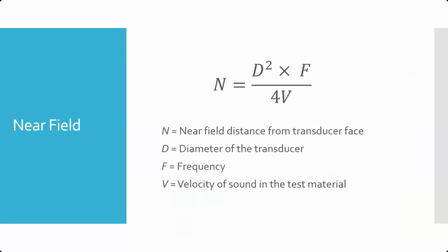So near field, right, the distance of near field, this is the distance from the transducer face. And remember, this is the transducer face, so part of this is going to occur in that wear plate area, right? It's not going to be from the surface of the part, but you have to take into account how thick that wear plate is. The near field distance is equal to the diameter of the transducer squared times the frequency divided by 4 times the velocity of sound in the test material.